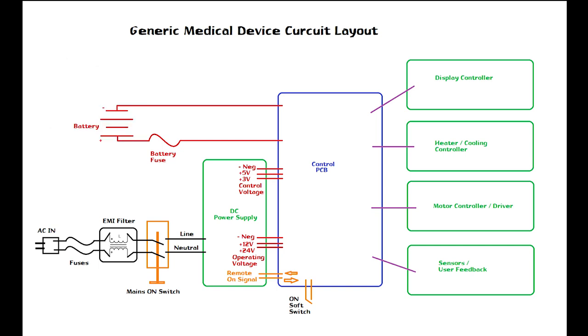The control PCB usually acts as a battery maintainer and battery charge circuit. So notice the battery is not usually connected to the DC power supply. It's usually connected to the control PCB, which monitors and maintains the battery.